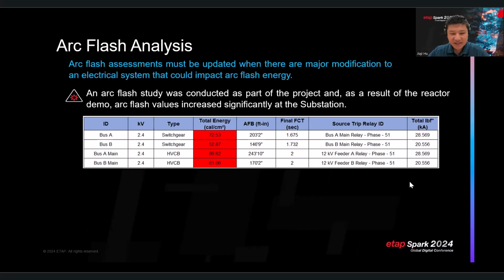The second is that the substation relays are old electromechanical relays, and only the time overcurrent function is enabled at this stage for better coordination with downstream. So with time overcurrent, the 4 locations all got a very long FCT to clear the fault. So they got a high incident energy here.